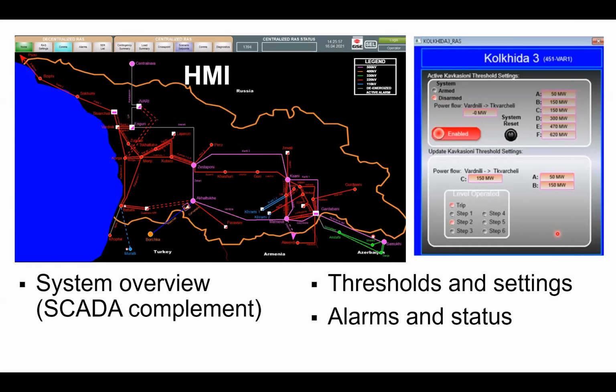We decided not to overload the SCADA system because the dispatcher, during dispatching, of course does not really deal with the ECS HMI. The ECS system is a very fast system, which operates automatically. Only in the case when the dispatcher's involvement or interference is necessary for the ECS system, which is only when we have a change in the system of the power flow. Therefore, we decided that there is no real need for ECS signals to appear on a SCADA dispatcher's HMI screen. Thank you for the question.